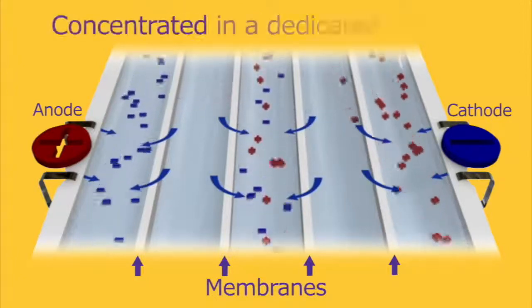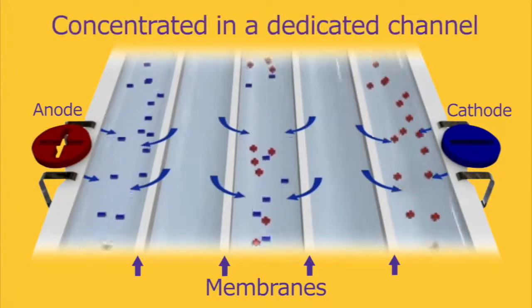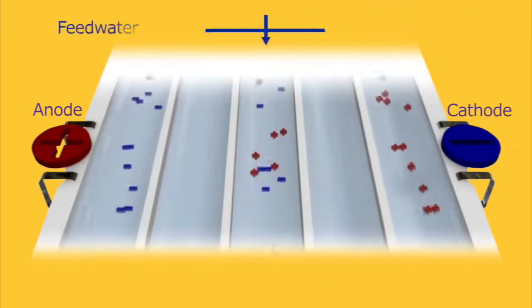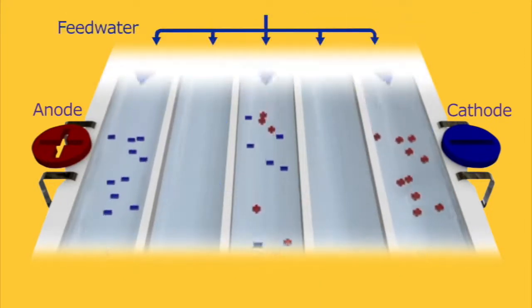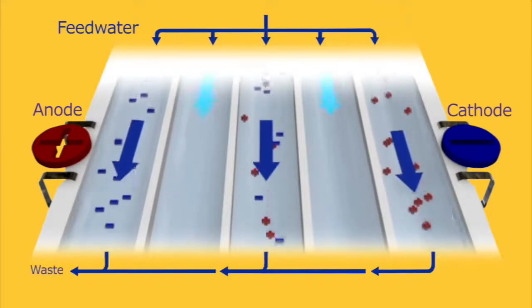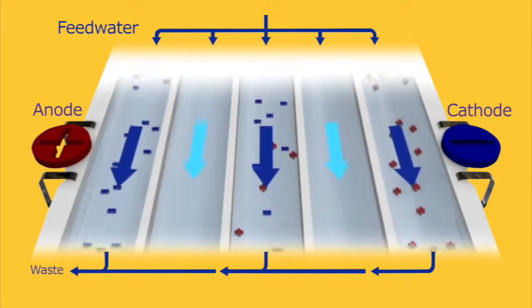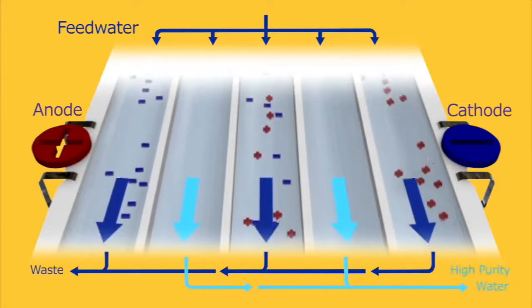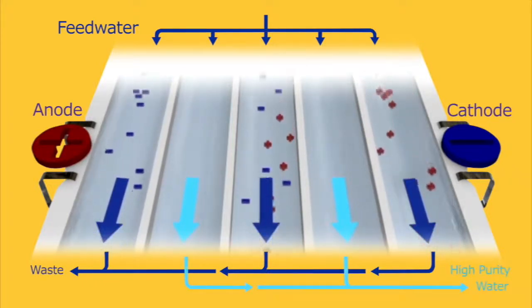Water molecules are left behind, resulting in a concentration of ions in a dedicated channel. The ions are collected and removed in a small waste stream, whereas the water molecules are gathered into a deionized path flow. The resulting purified water is then available for your applications.